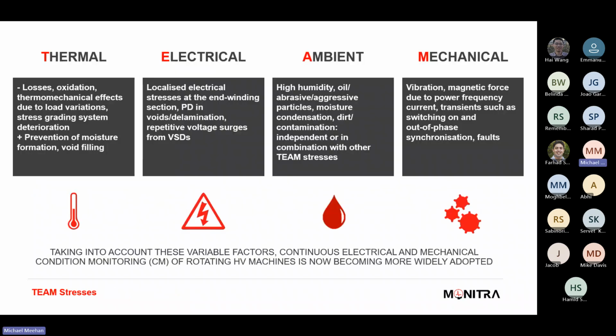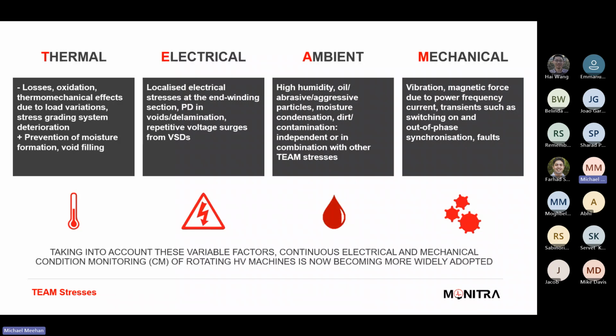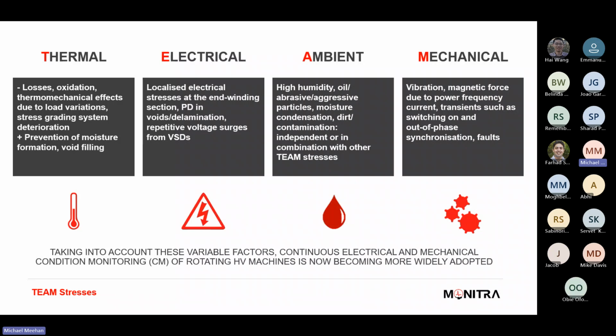So when we think of the failure modes, a very common reference used is the TEAM stresses. If we think of these as individual failure modes, the first is clearly identified as thermal. Temperature on a machine is one of the biggest and most common failure modes, because the insulation medium itself does not like to be put under extensive temperatures. It can become brittle, it can start to crack, it can then start to contain moisture and reduce the insulation properties of the actual insulating medium. So temperature, due to the copper losses I squared R, eddy currents, stray losses plus core losses, leads to insulation aging.